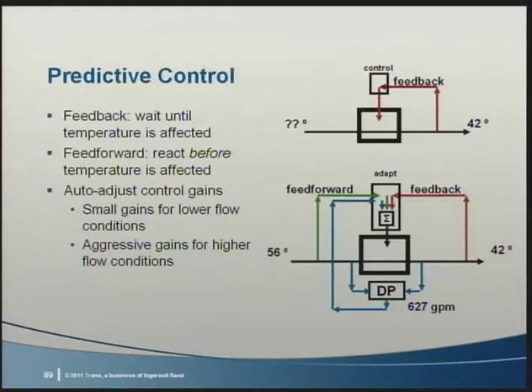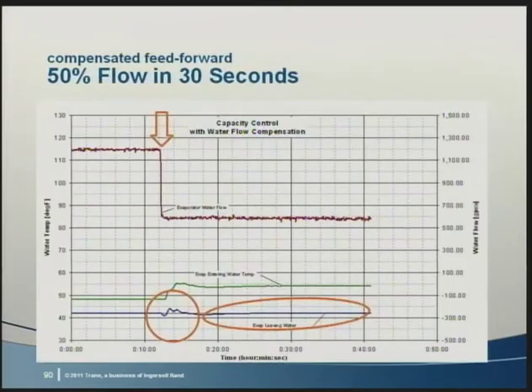So building upon this, compensating controls use algorithms to auto-adjust and provide the most effective control, since they easily overcome the variations that will result from normal operations and significant flow changes. If we compare a compensated feed-forward control to the previous system, you can see how much more stable the leaving water temperature is, even with a dramatic reduction in flow in a short period. Not only did the chiller stay online, but its chilled water temperature changed very little. This is the type of control now available for use in variable primary flow systems.